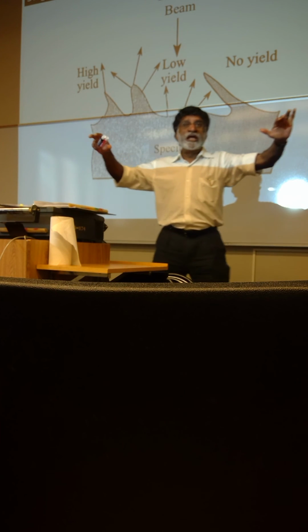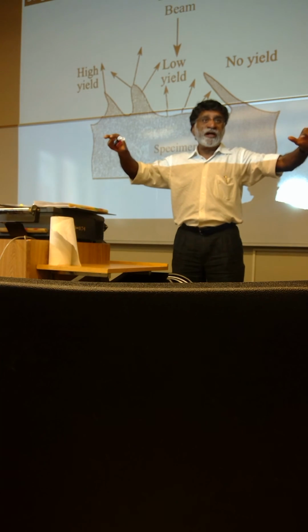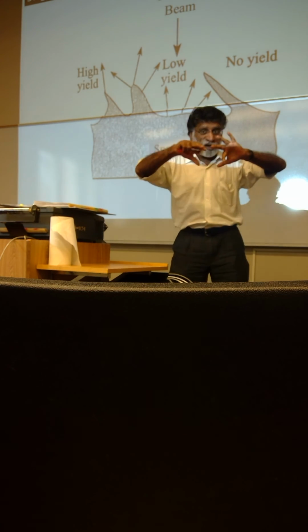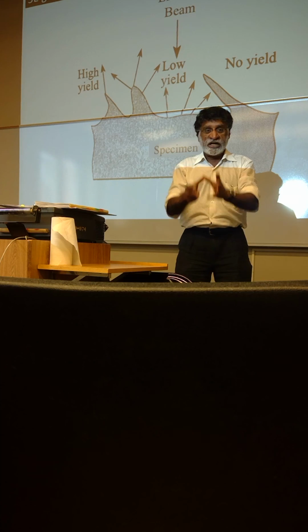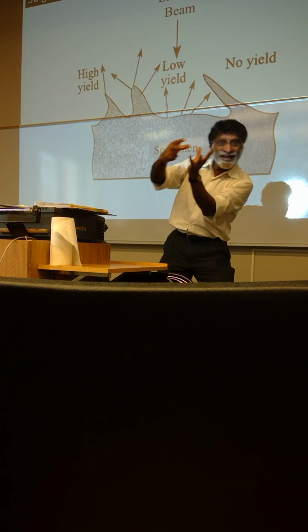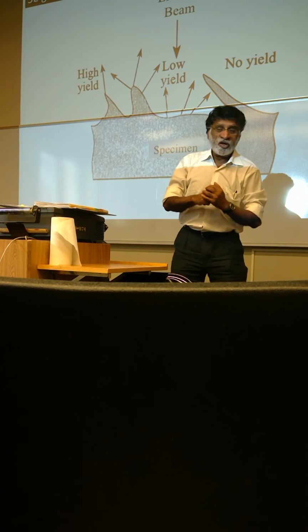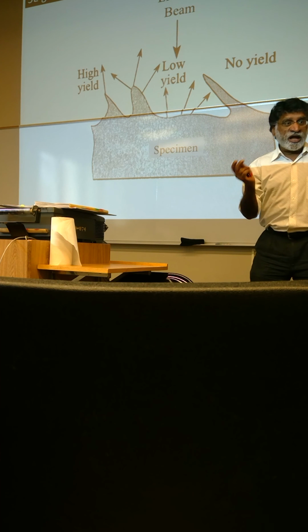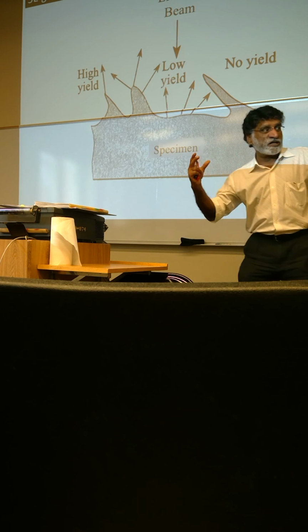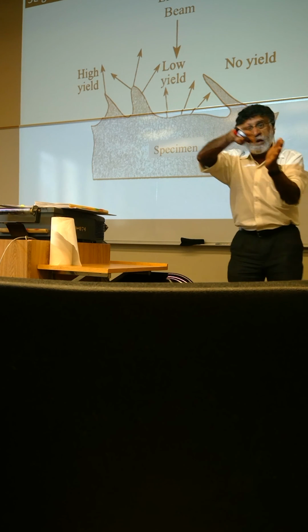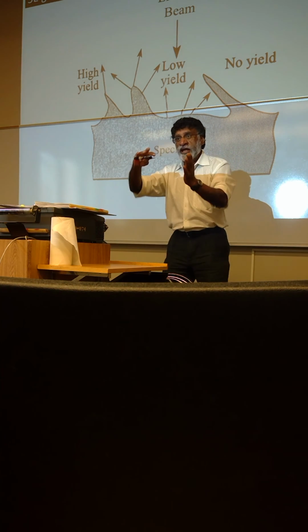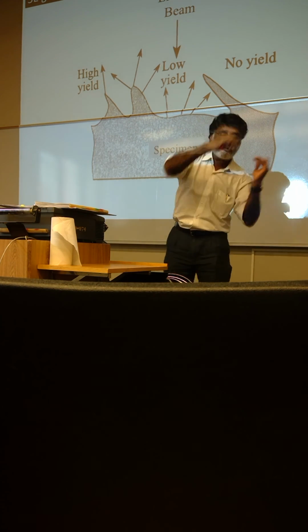So the topography is, for example, as you can see, you have a certain beam, just like you have oblique incidence in the optical microscope. The topography will generate different amounts of electrons in the direction of the detector. So the detector is placed here, and if the sample is tilted towards the detector, more of these will come. So if the sample has different orientation, then the topography will change the amount of electrons detected.